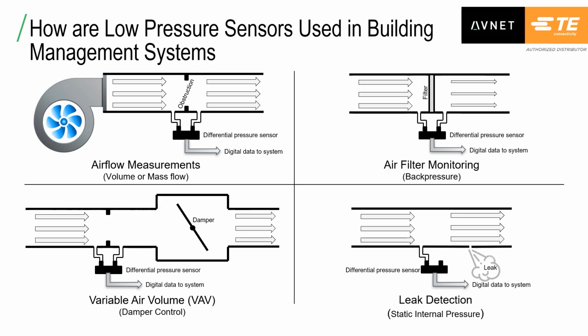The next major application is for air filter monitoring. While the algorithms are rather complex, monitoring the differential pressure across a filter can help determine when the filter is dirty, clogged, or damaged. Ensuring clean, efficient filters in a building can save a great deal of time and money, and can also help ensure occupant comfort and safety from contaminants. The next major application is variable air volume, or VAV, systems. The temperature of the supply air is held constant and the room temperature is controlled by varying the volume of air delivered. These systems are more efficient than constant volume, variable temperature systems.